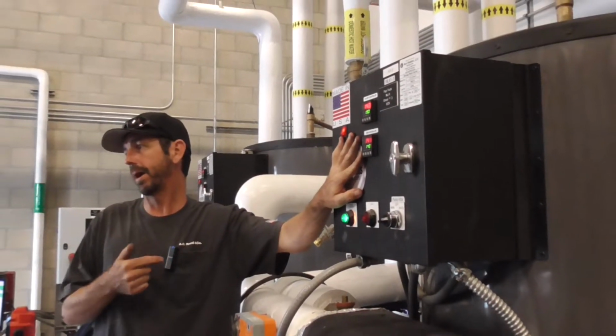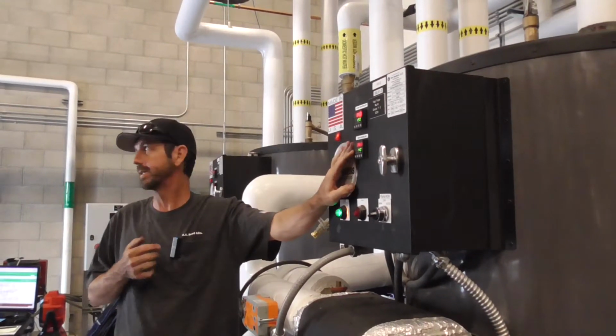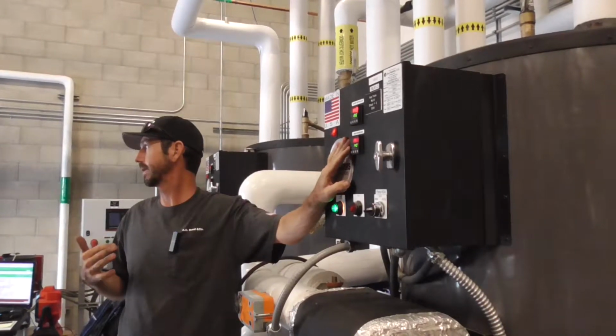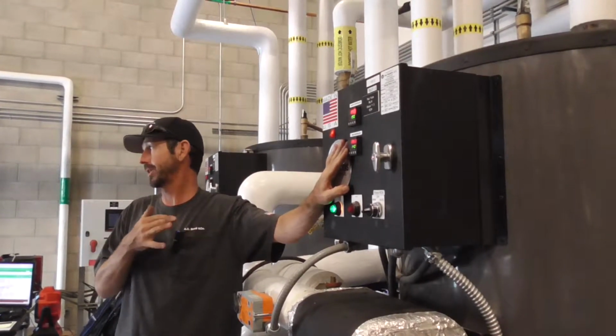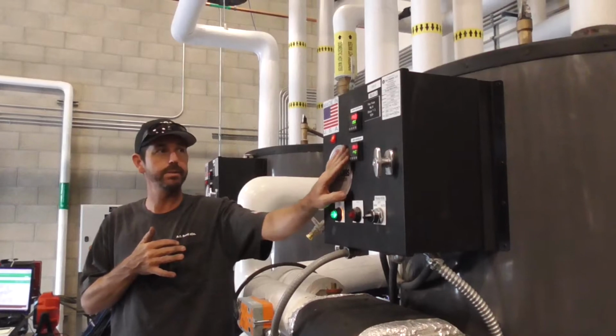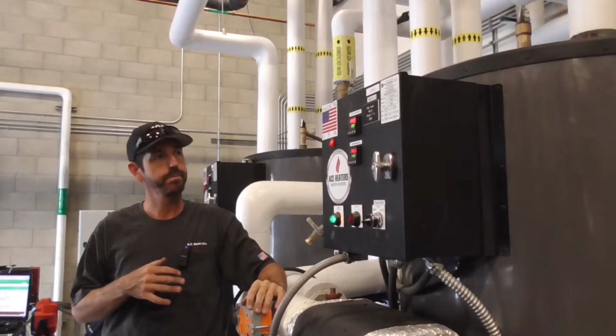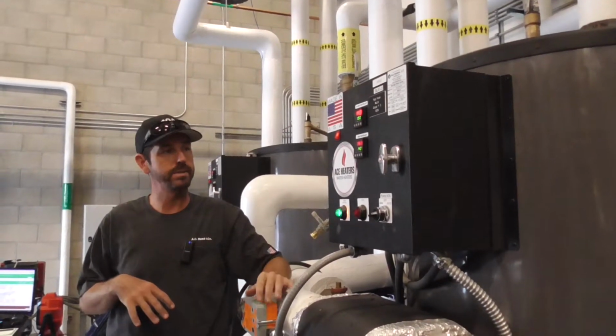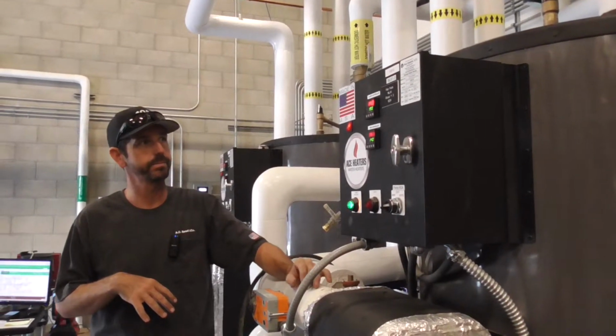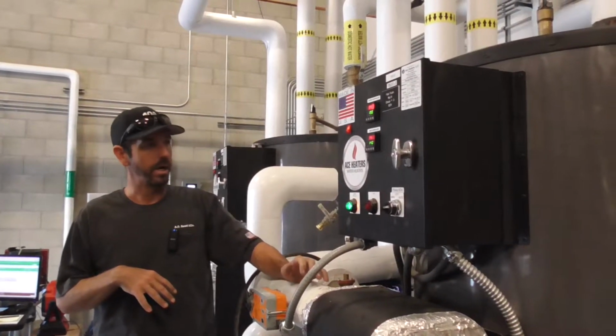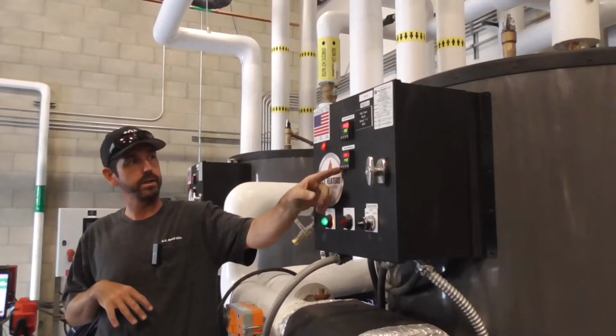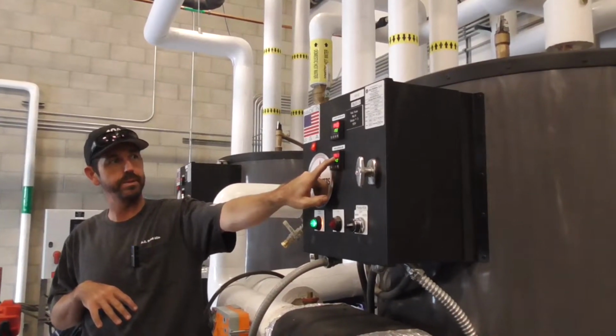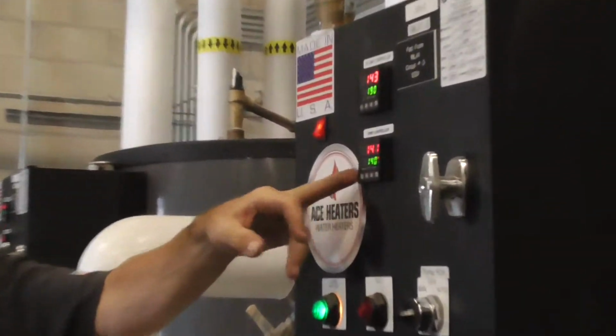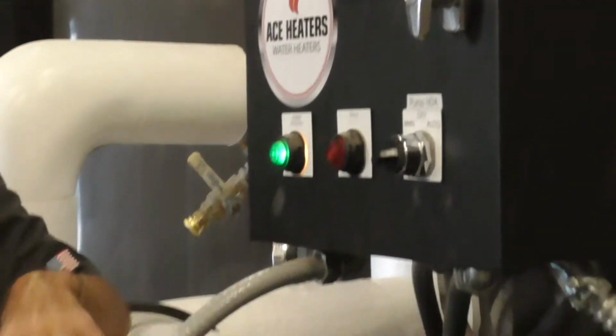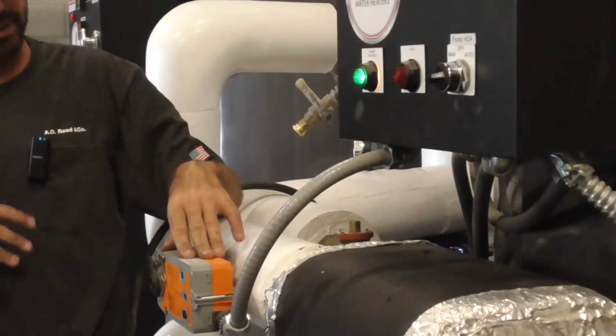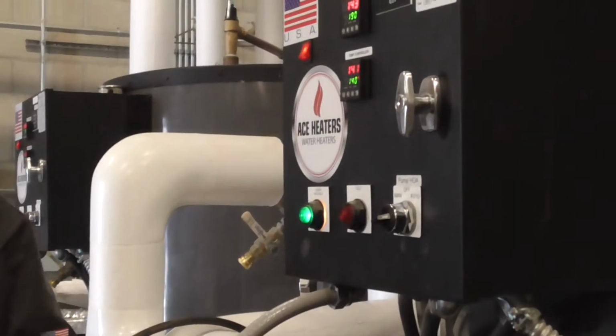This is domestic hot water, and we have a storage tank, so we're using 140 as our set point for Legionella, okay? So we want to make sure the tank maintains the 140 degrees to reduce the odds of growing bacteria, okay? Again, this is our temperature set point. This is our actual temperature. The controller here sends a signal to the valve. Okay? This valve modulates open and close depending how far away from the set point it is.